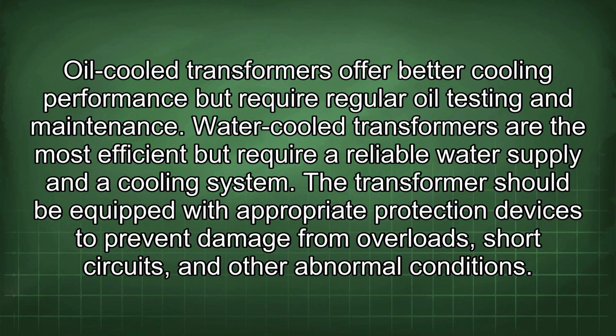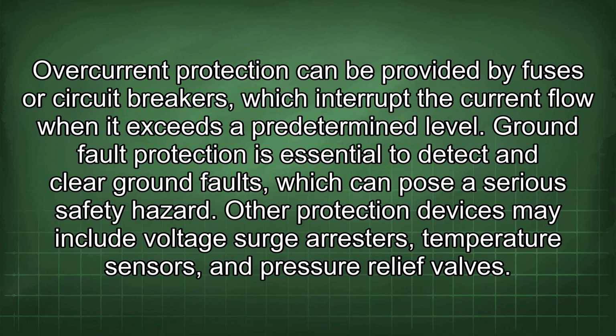The transformer should be equipped with appropriate protection devices to prevent damage from overloads, short circuits, and other abnormal conditions. Overcurrent protection can be provided by fuses or circuit breakers, which interrupt the current flow when it exceeds a predetermined level. Ground fault protection is essential to detect and clear ground faults, which can pose a serious safety hazard. Other protection devices may include voltage surge arresters, temperature sensors, and pressure relief valves.